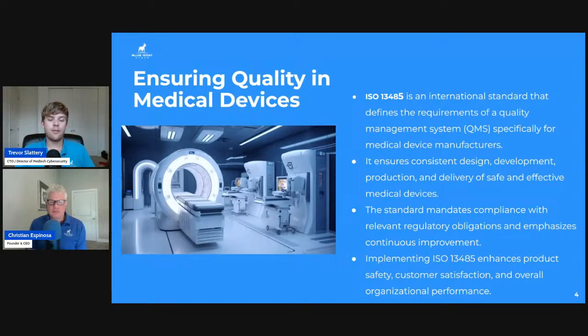Now, to sort of summarize everything that we're doing with ISO 13485 here, we're looking at product safety, satisfaction, performance. This is through consistency. This is through traceable design. This is through traceable history of documentation and sufficient documentation. We always say that every engineer's worst nightmare is having to write documentation on their code. And while it can be tedious for many to prepare some of these artifacts, it is vital, especially in the regulatory space, when we need to present to the regulatory authority how we develop this product and all of the artifacts that are required to go along in that submission.